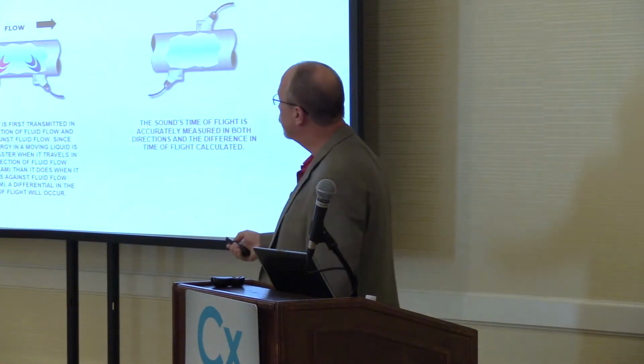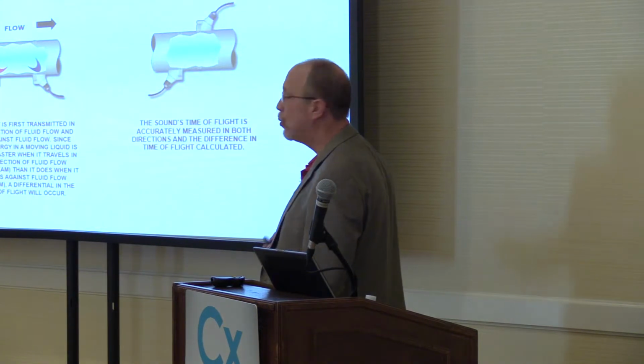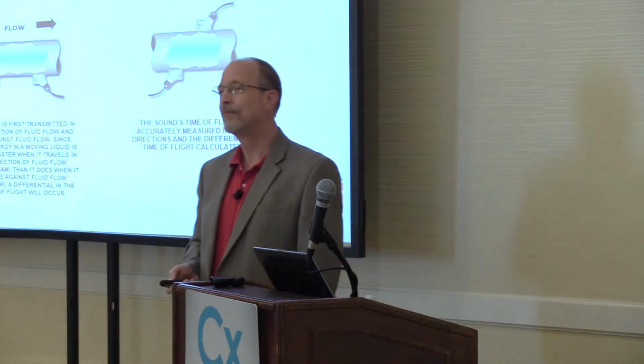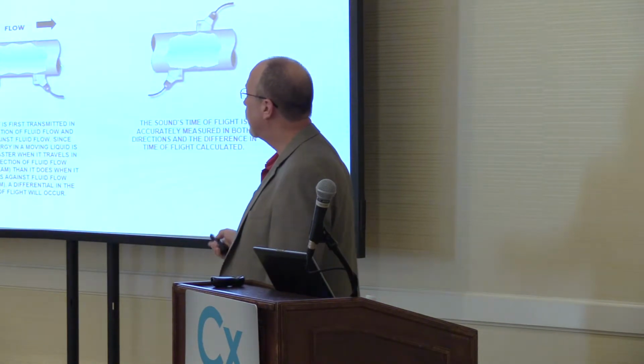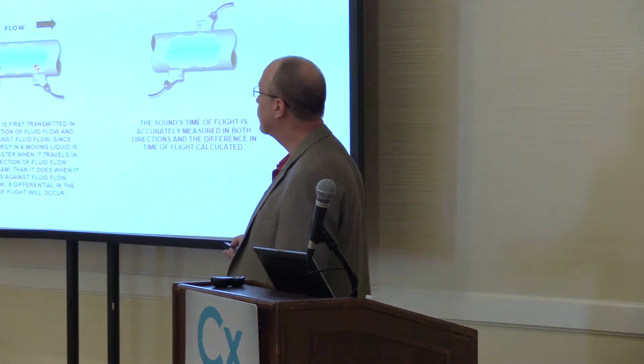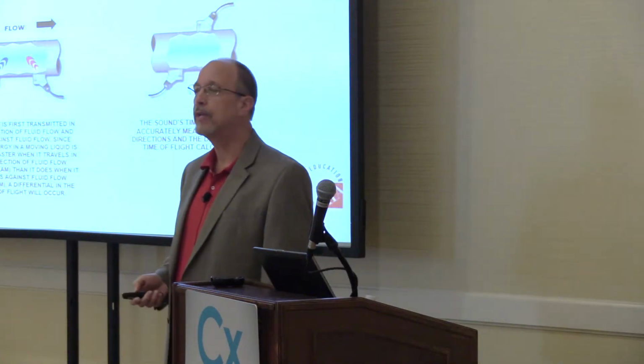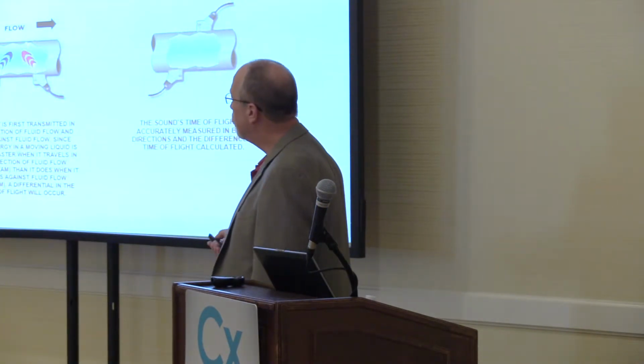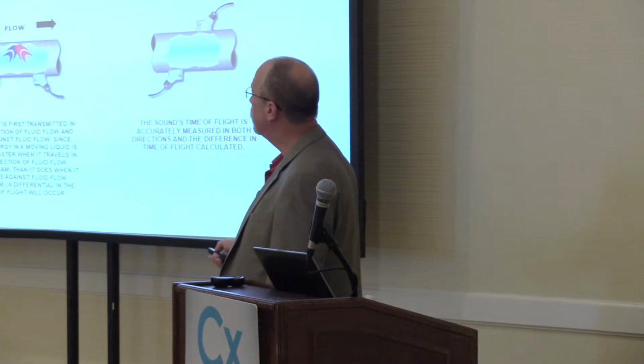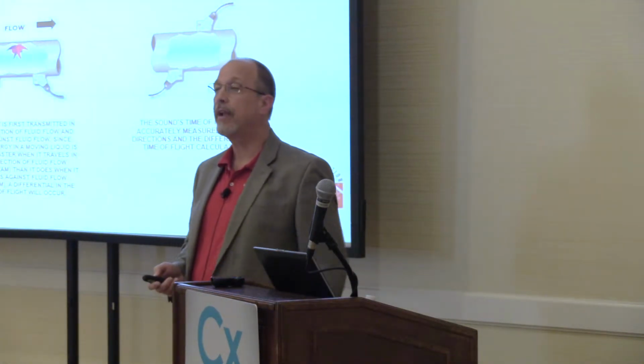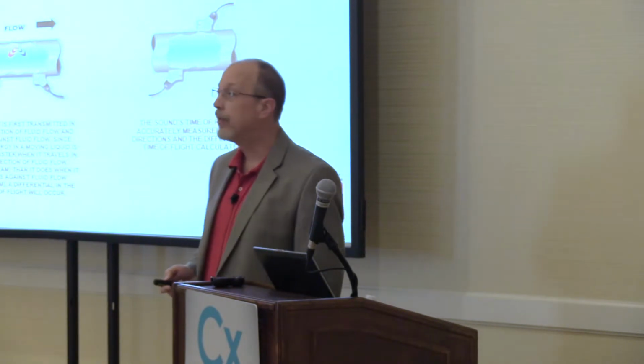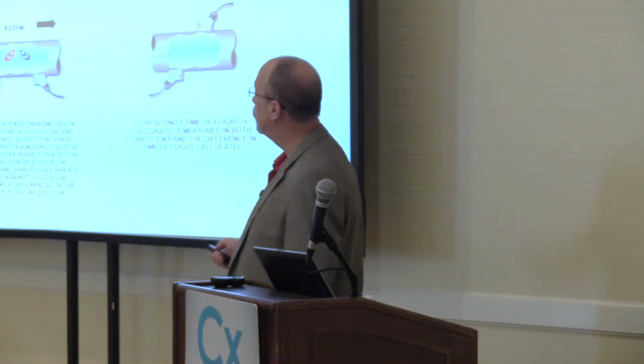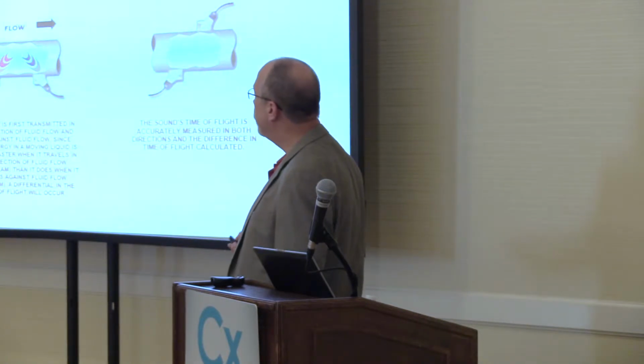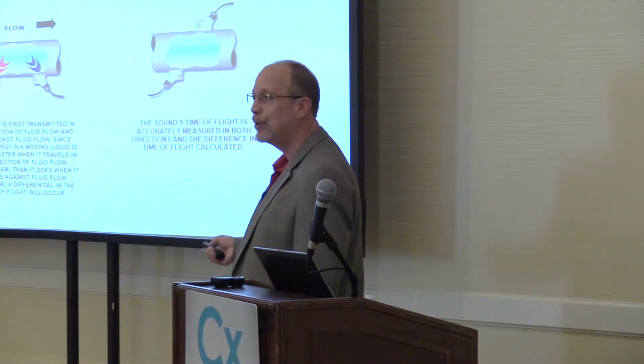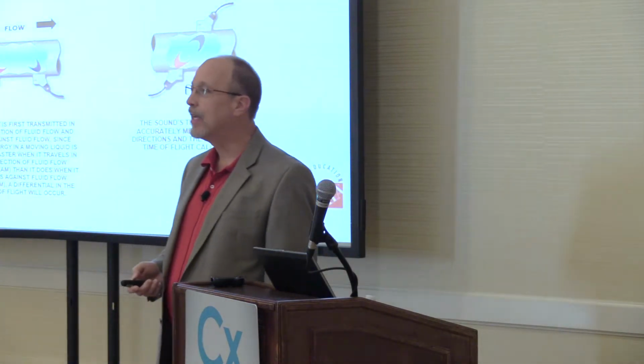As for the transducer position, you don't normally see this configuration with one on each side of the pipe because it's harder to do. What we normally see is this configuration, where the flow is going from left to right. We have two sensors on the side of the pipe, one sending a sound beam here and ricocheting off the back wall to the other transducer downstream. And then again, it sends a signal back here and here. This configuration is traditionally called the V configuration, or in some brands, the dual path. There are other names for it as well, but it's basically two beams from here to here. And we do this configuration because we're lazy. Both transducers are on the same side of the pipe, and so we can see the installation.